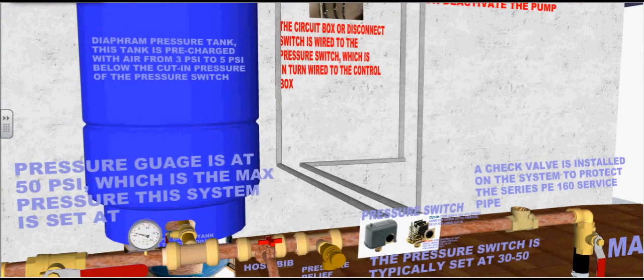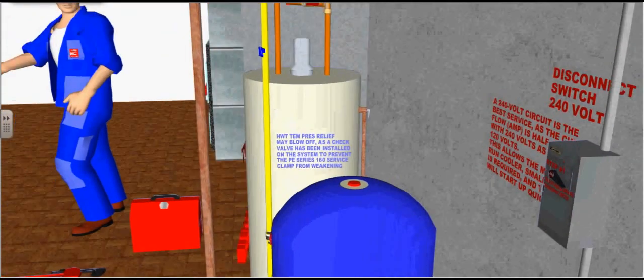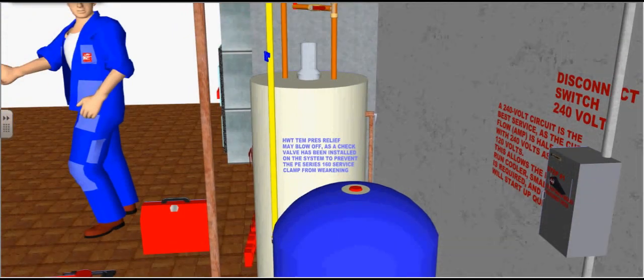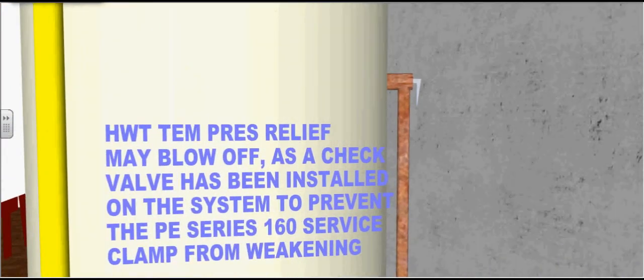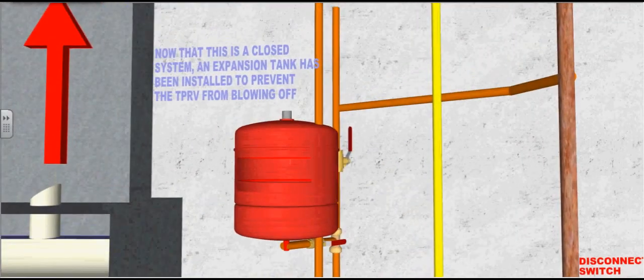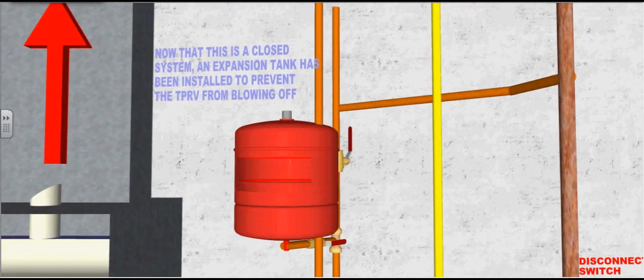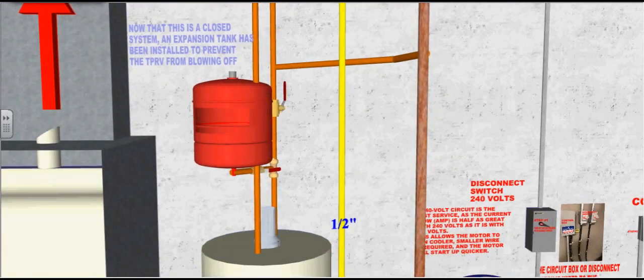The diaphragm pressure tank is pre-charged with air from 3 to 5 PSI below the cut-in pressure of the pressure switch. This hot water tank temperature pressure relief valve may blow off, as a check valve has been installed in the system to prevent the polyethylene series 160 service pipe from weakening. Now that this is a closed system, an expansion tank has been installed to prevent the temperature pressure relief valve from blowing off.